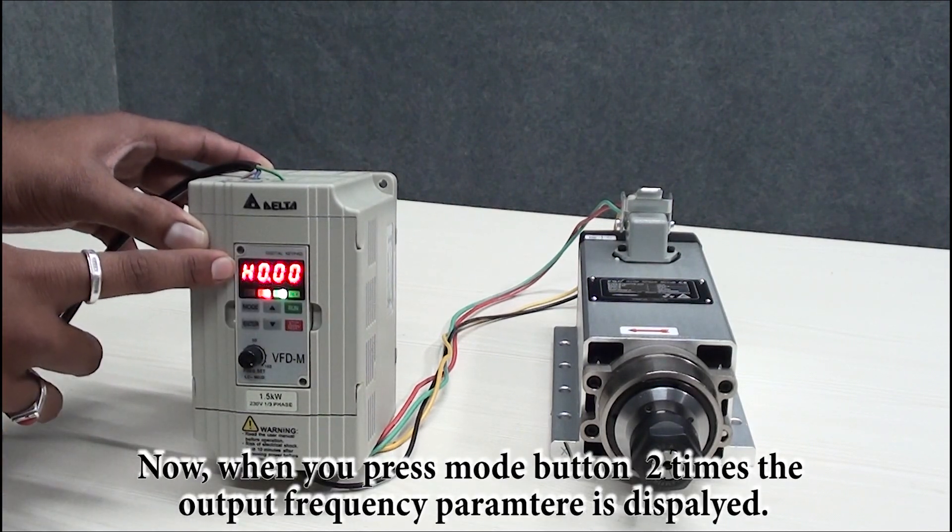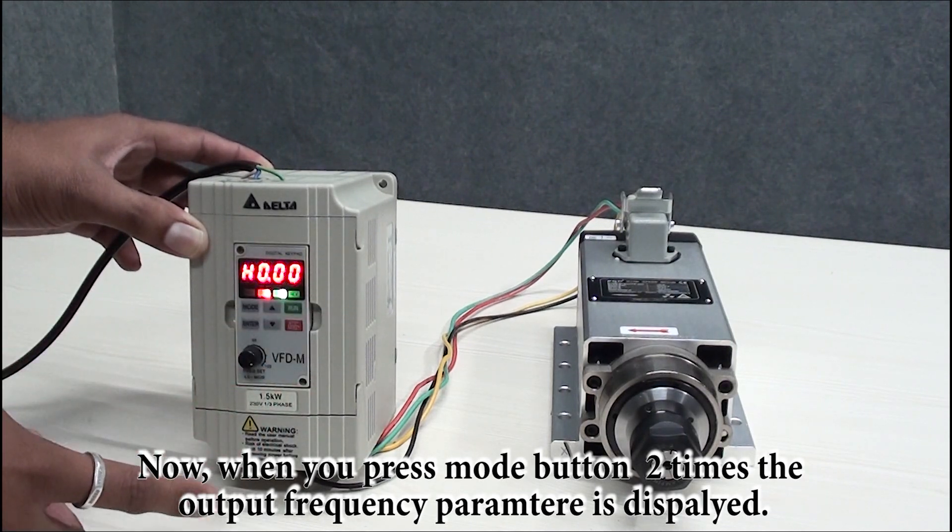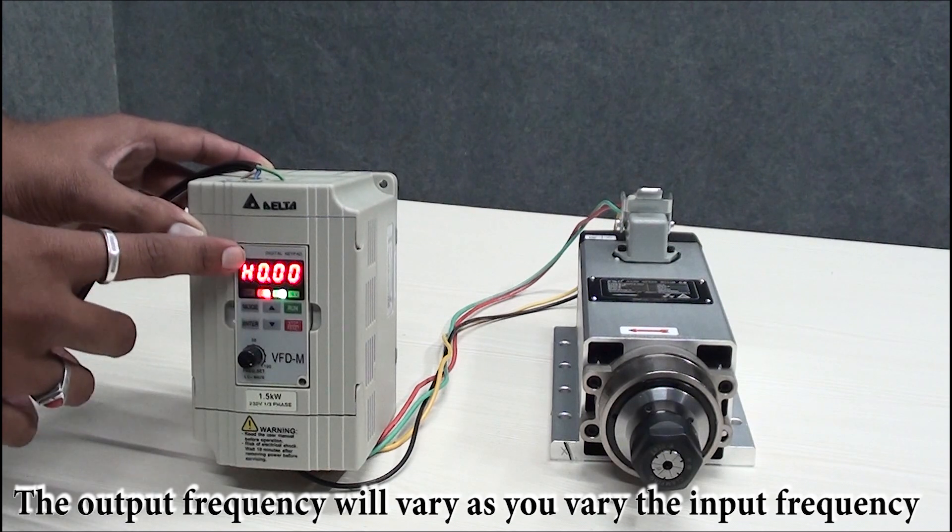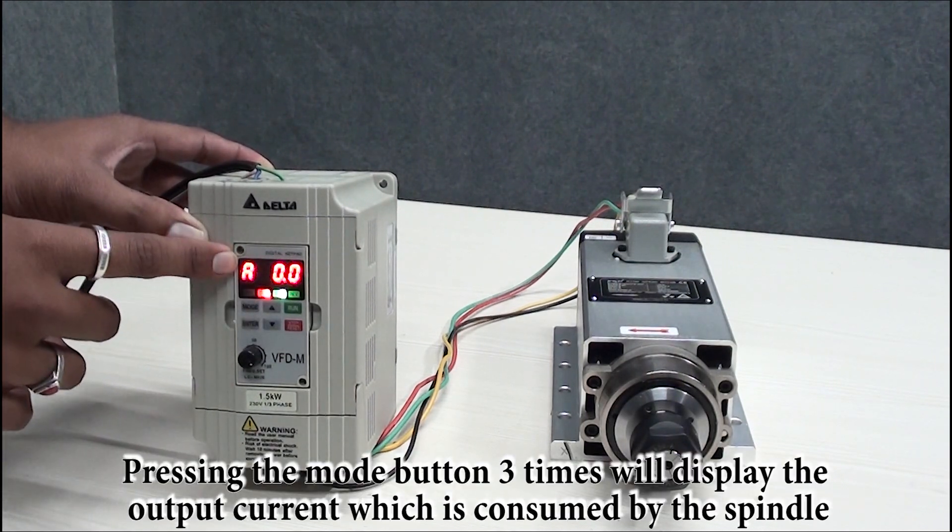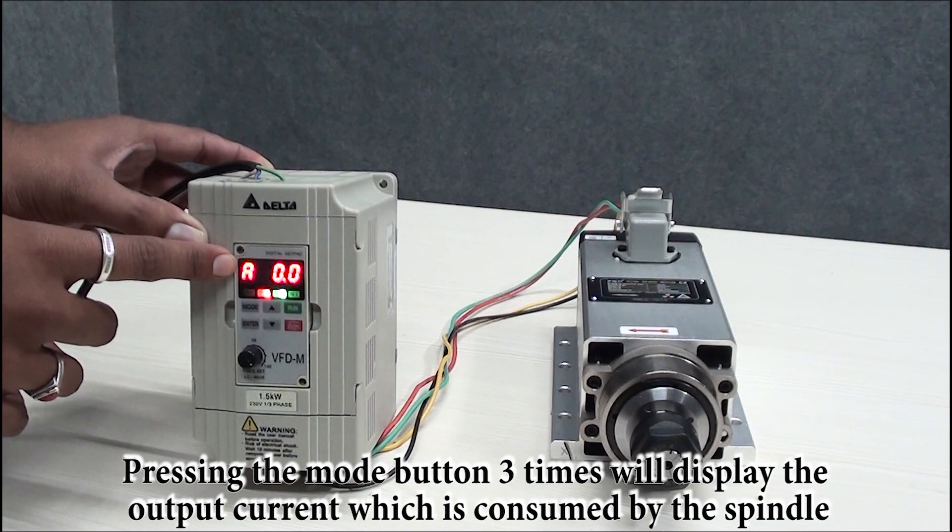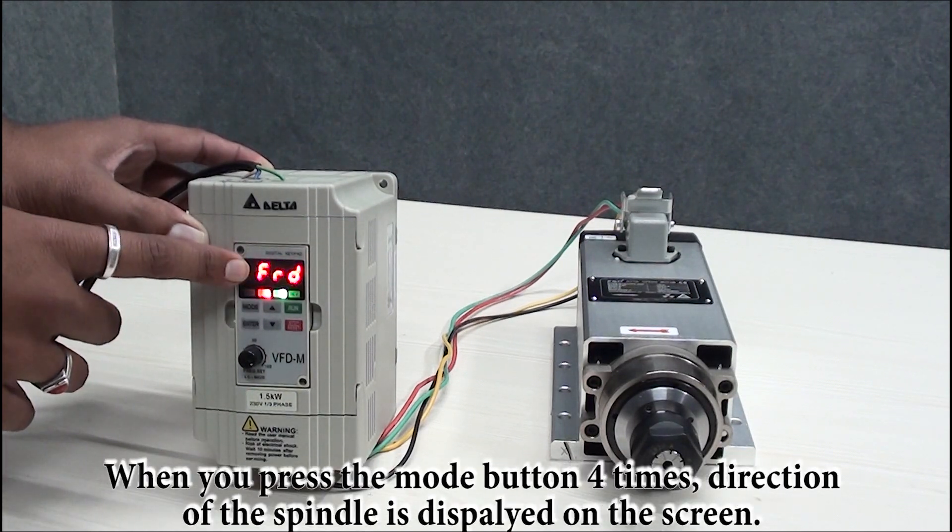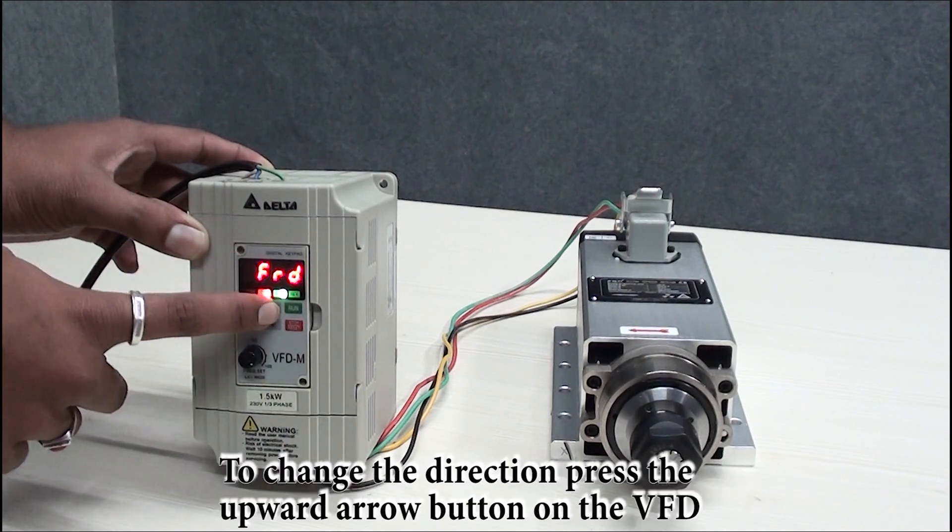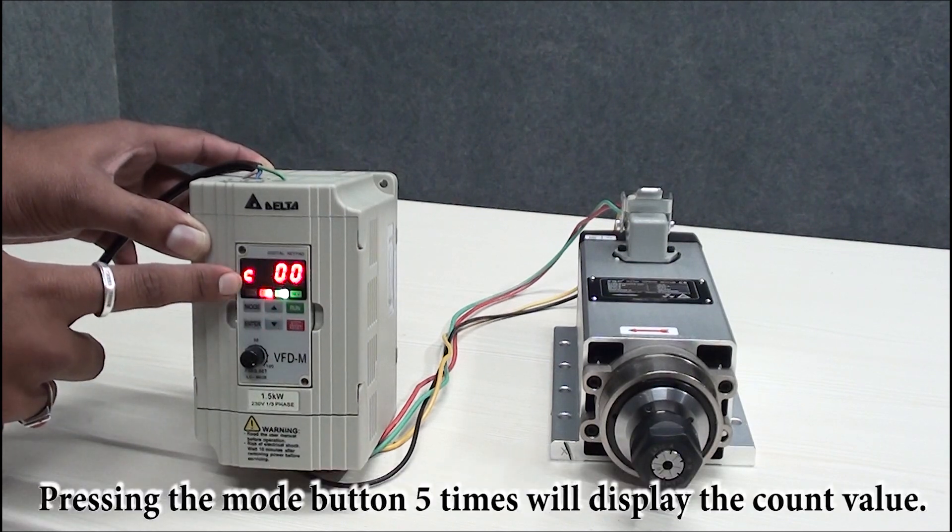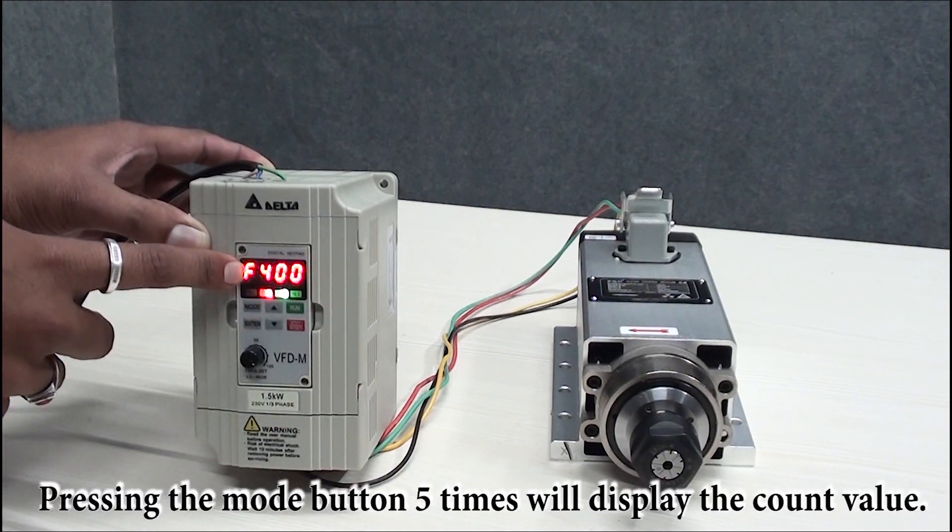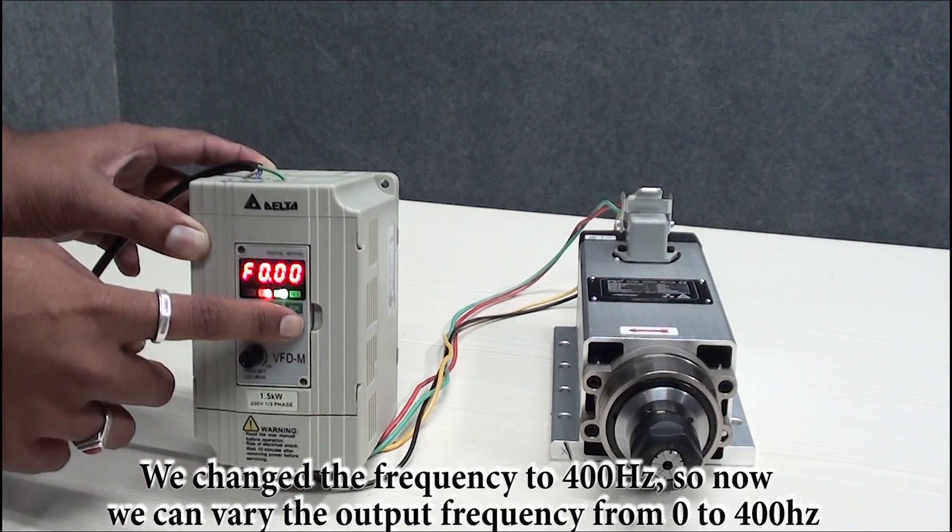Press mode button again. H is the output frequency which will be supplied to spindle by VFD at the output U, V, W. It will vary as you vary the input frequency which is master frequency. A is the current, it will show the output current of the spindle which is consumed by spindle. Direction will show FRD means forward direction. As you change from here, REV will be reverse direction. C is for counter value.